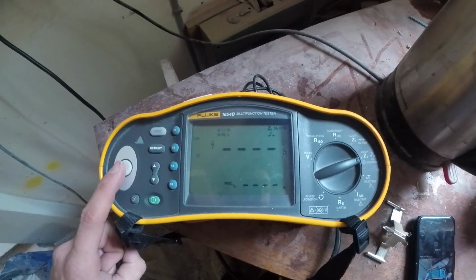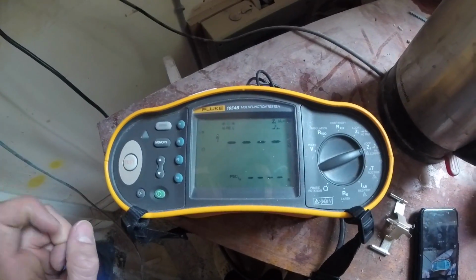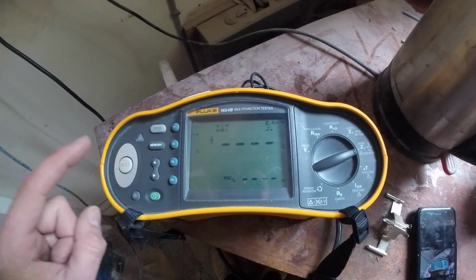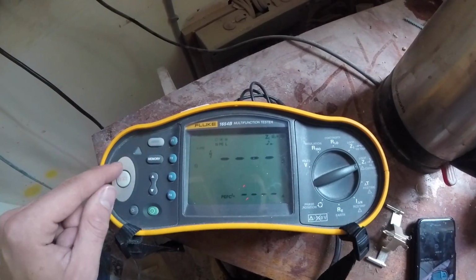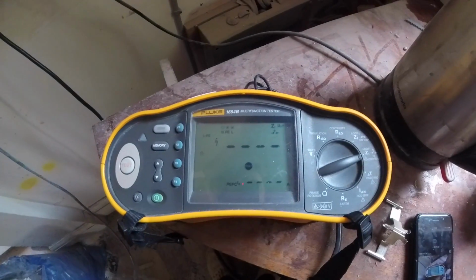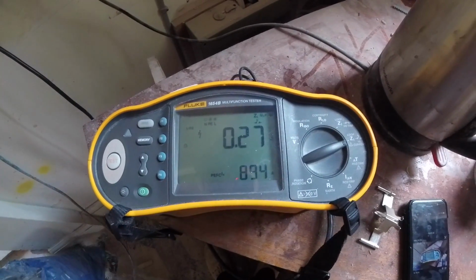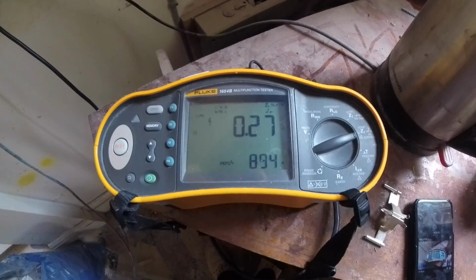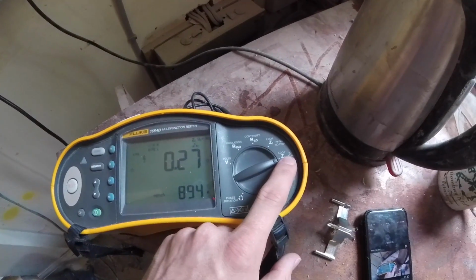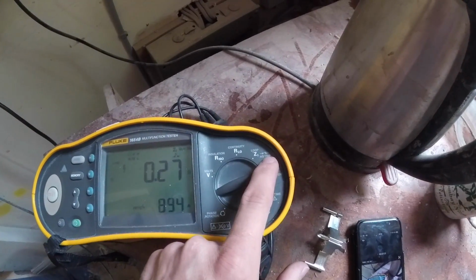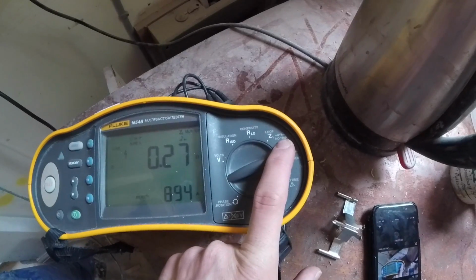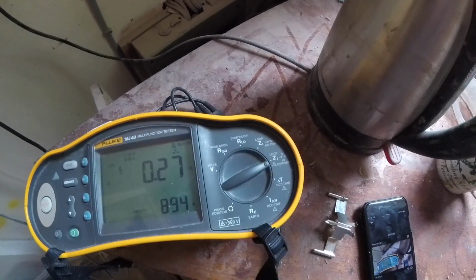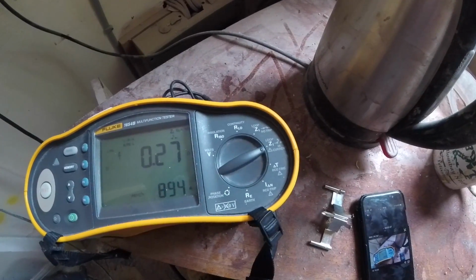And while I'm here, I'm going to put you on to the high current test and just show you how much quicker it is on the high current. But if you have got an RCD on the circuit, it will trip it out straight away. So change that back to live PE. And there we go, 0.27, done quick as that. So yeah, the high current is obviously a lot quicker. The no trip is slower, but that does save it tripping out any RCDs if they are protecting the circuit.